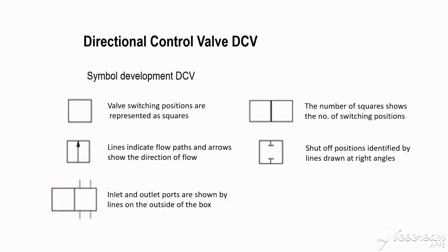For the directional control valve symbol: a two-position valve is drawn as a rectangle divided into two sections. The right side represents the normal position and the left side represents the activated position — what position the valve transfers to when activated.